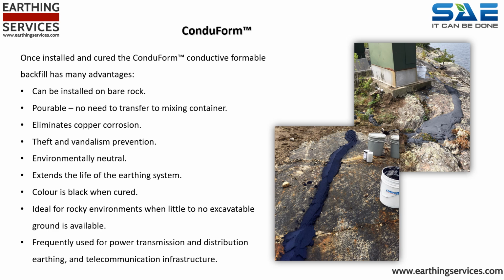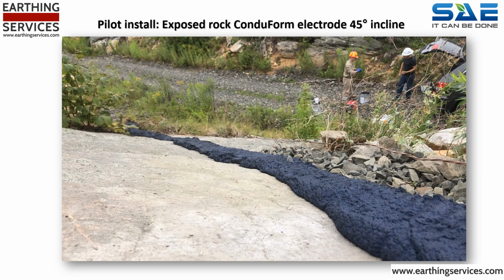As you might imagine, it is far easier to cover a conductor than it is to excavate down to install one. If required, berming can disguise the ConduForm for aesthetic reasons. Here we see ConduForm installed on a bare rock on a 45-degree angle. Other products would simply slide off, but ConduForm holds firm and then solidifies. In this given example, they had tried to use regular concrete, which did simply slide off. ConduForm has even been used in vertical applications where it was adhered around the surface of a large boulder and it held firm.